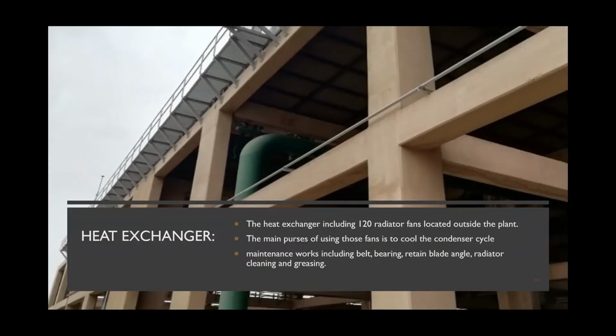Now let's talk about the heat exchanger, which includes 120 radiator fans located outside the plant. Due to the large space they need, the main purpose of using those fans is to cool the condenser cycle. Some of the maintenance work includes belt and bearing checks, retaining blade angle, radiator cleaning, and also bearing greasing.